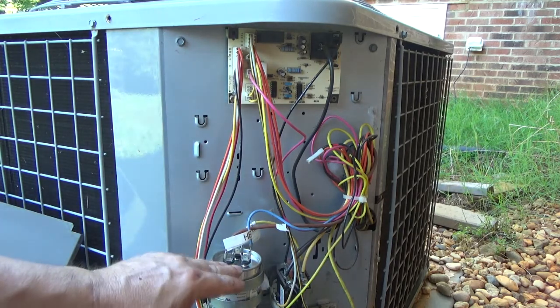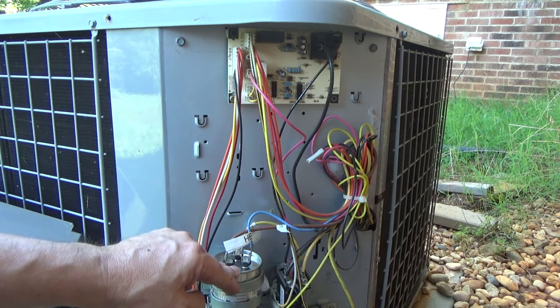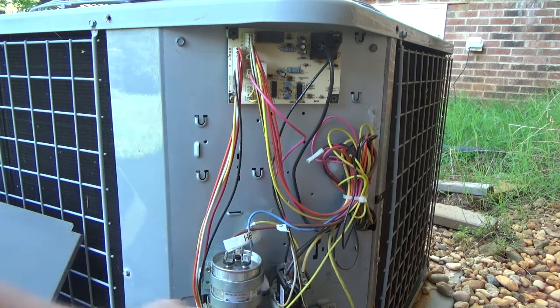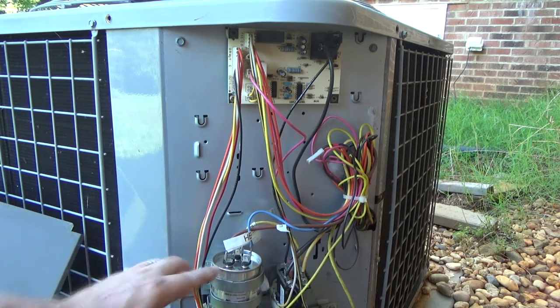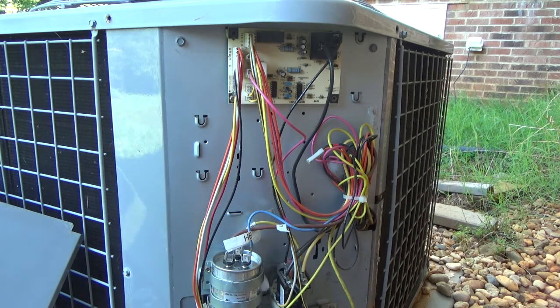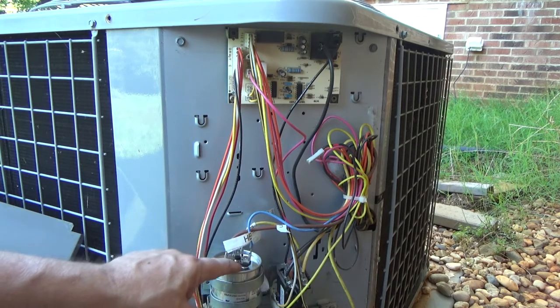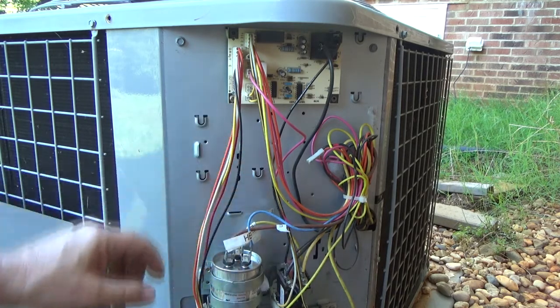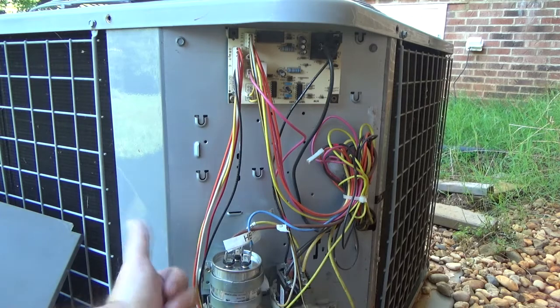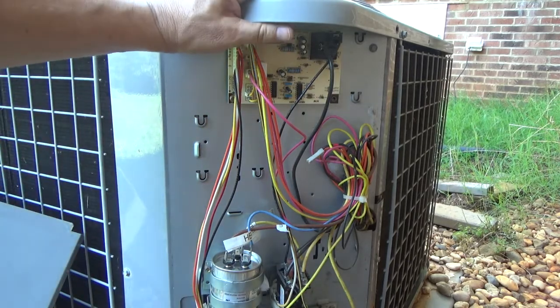The big one mainly for a homeowner is the relay being full of bugs, or the start capacitor has ended its life. It does that by having a big bubble—this plate here in the middle just bubbles right up, and your connectors are all off to the side. It's very easy to tell if that's gone bad.